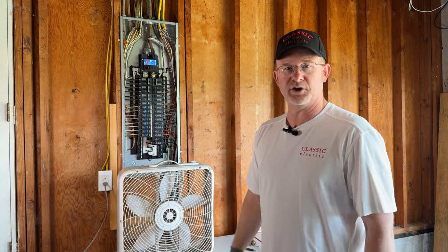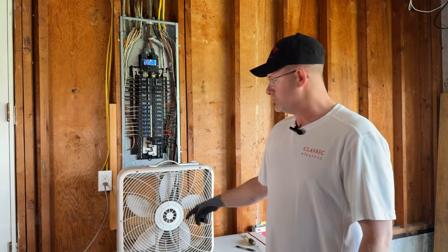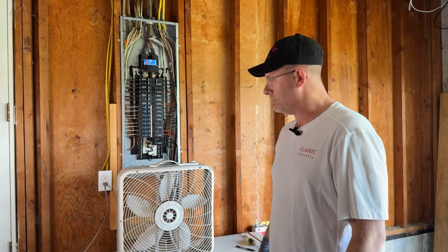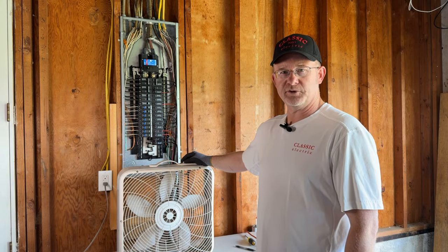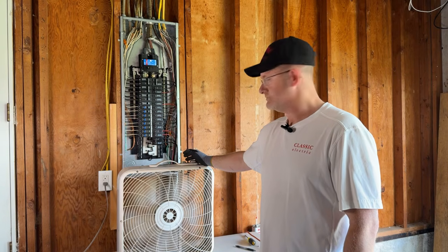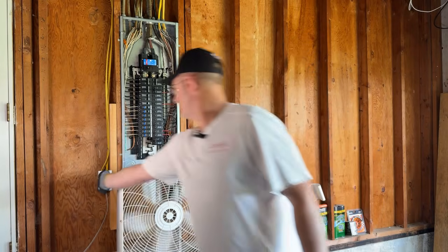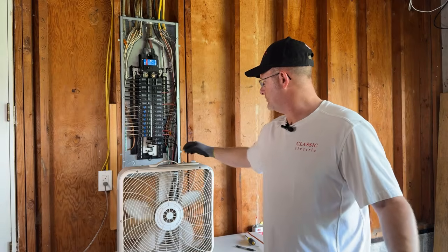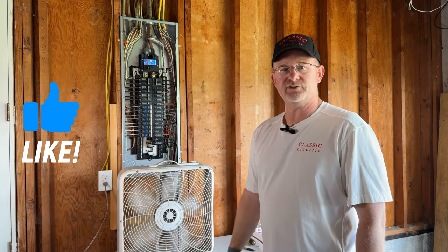But let me give you a demonstration of what happens with a GFCI, and in this particular application, with a bad motor. So let me show, and then I'll talk to you a little bit about what's going on. I'm going to go ahead and turn this on, and every time you turn it on, it just immediately shuts off. So I can do this all day, and I can keep resetting.